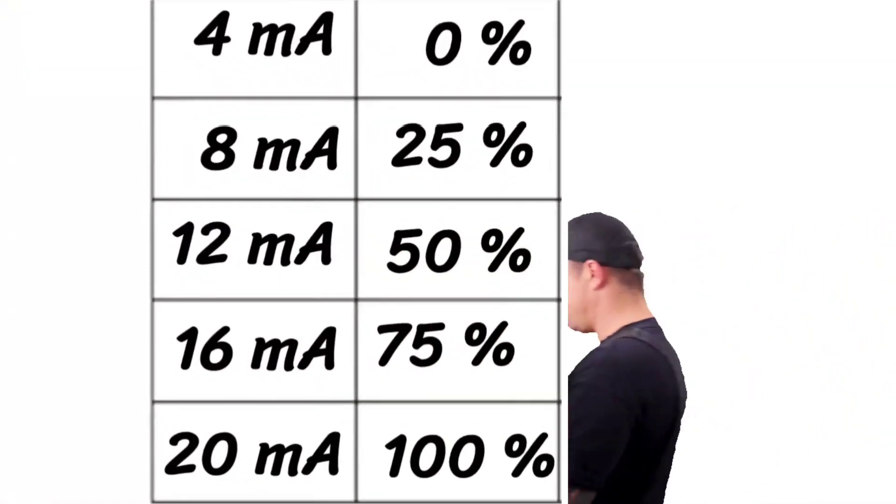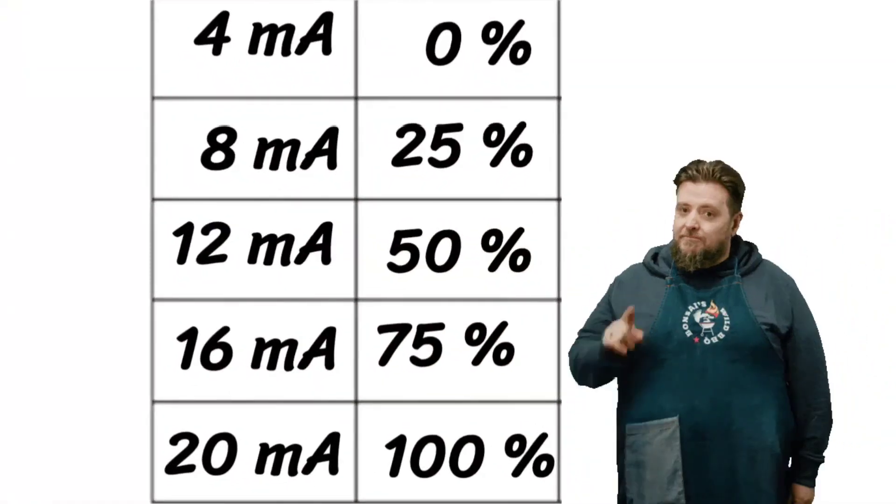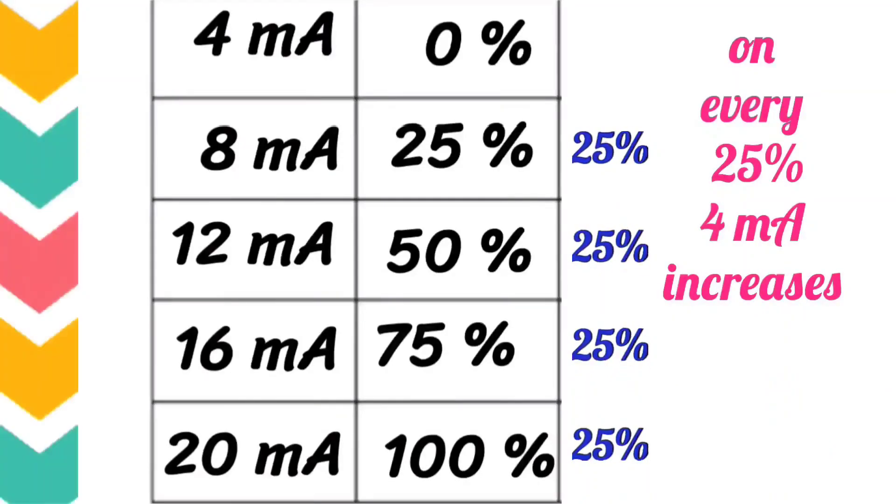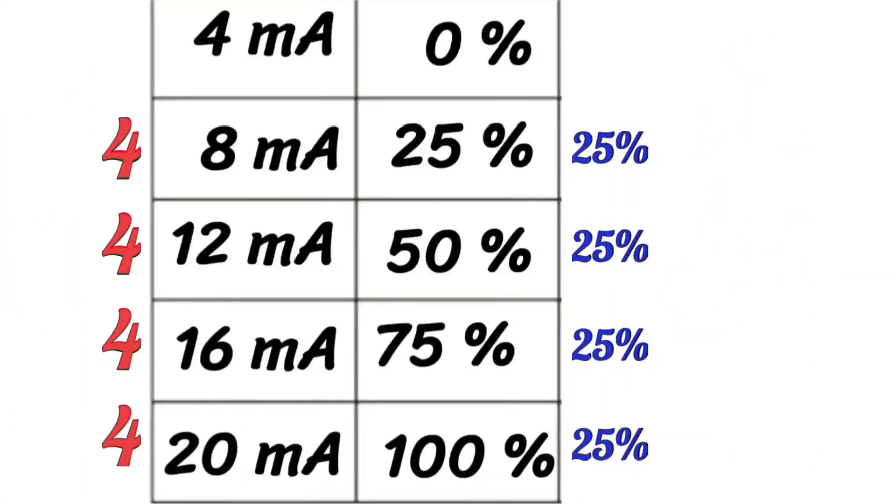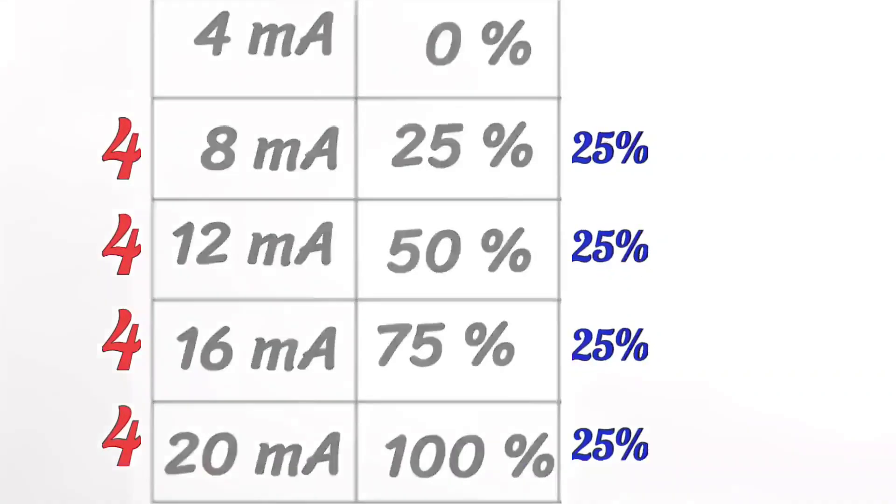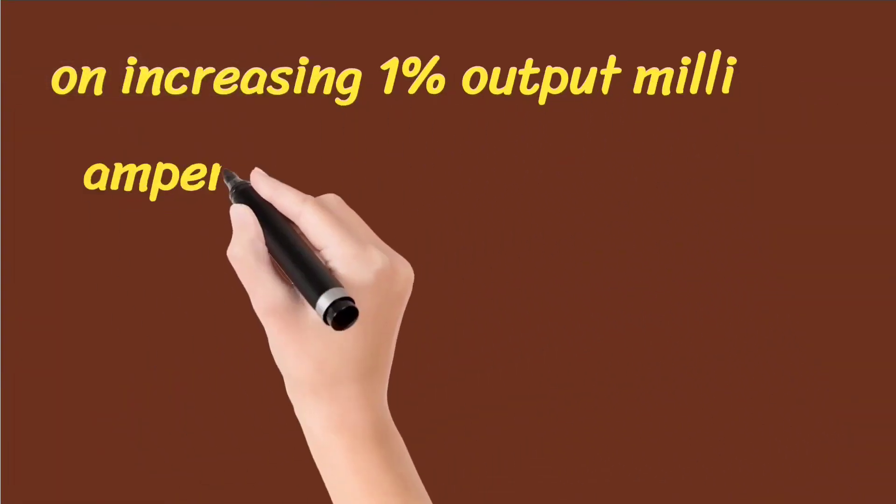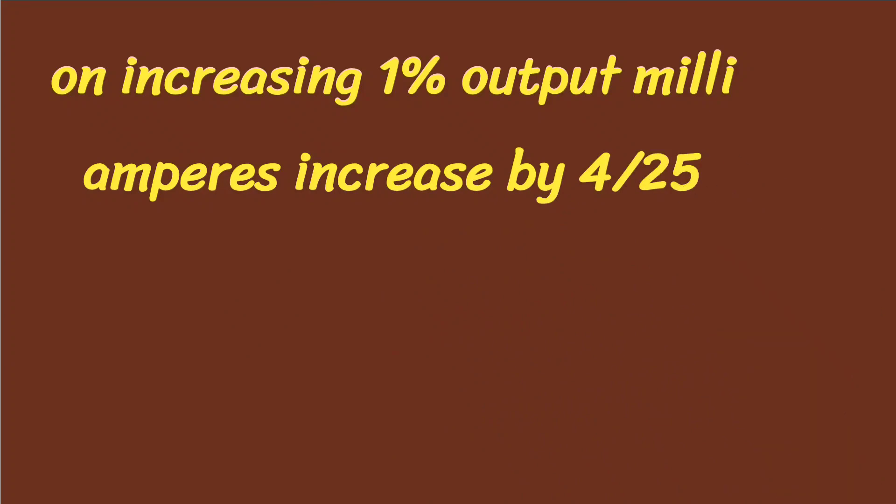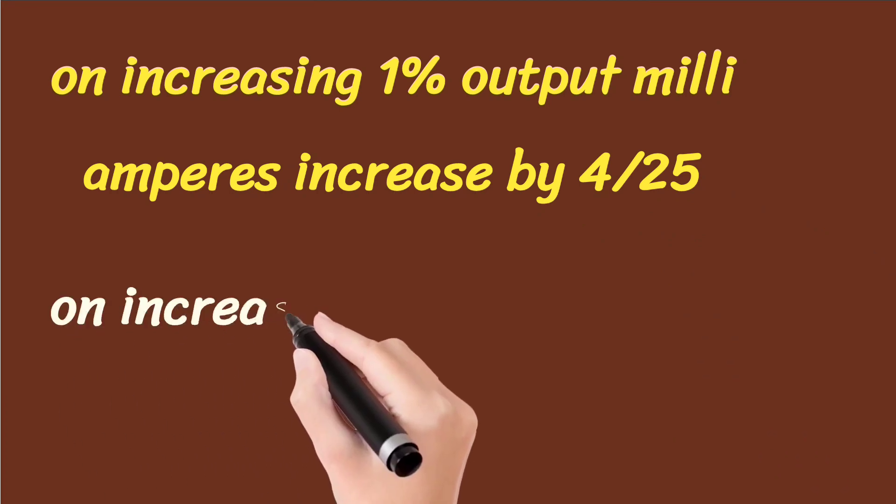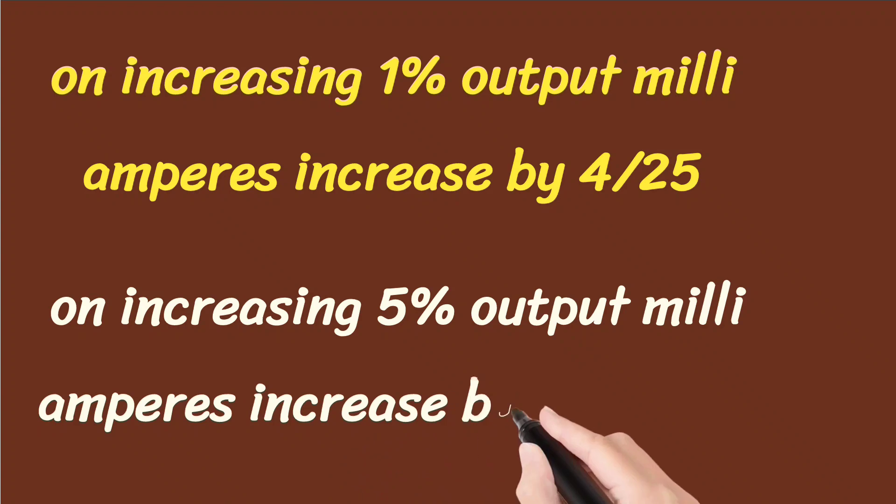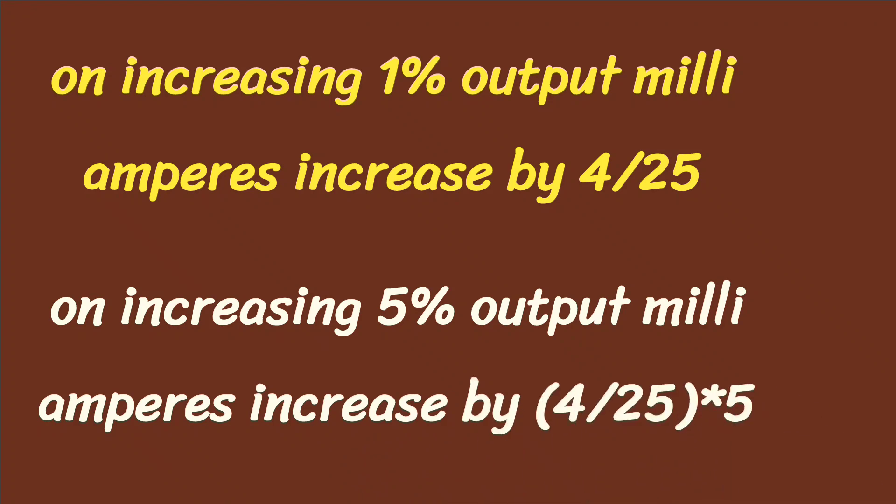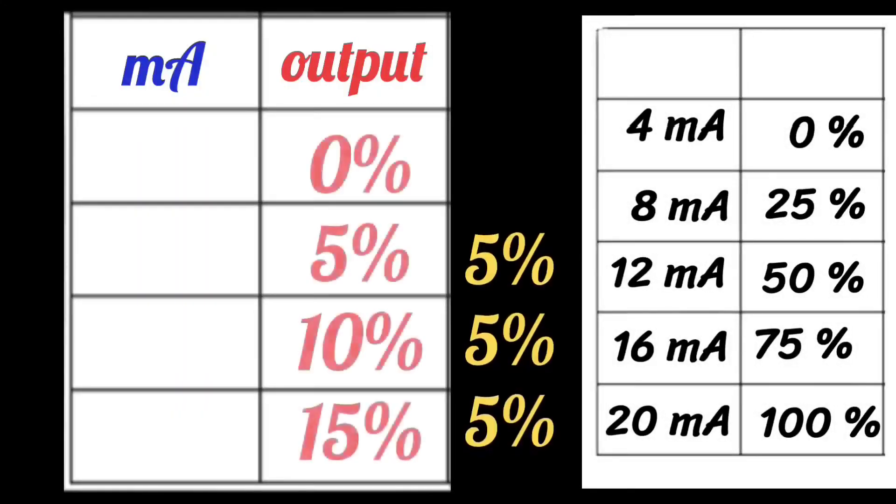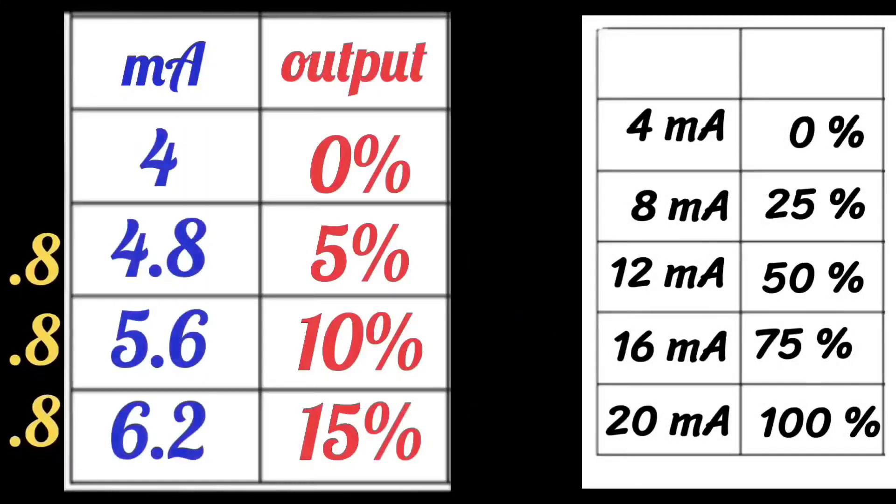Once when you look at the table carefully, for every 25% increase in output, 4 milliamperes are increasing. You can see this from beginning to end. On increasing the output by 1%, 4 divided by 25 milliamperes will increase. On increasing the output by 5%, 4 divided by 25 multiplied by 5 milliamperes will increase. That means 0.8 milliamperes will increase. So on each 5%, 0.8 milliamperes are increasing.